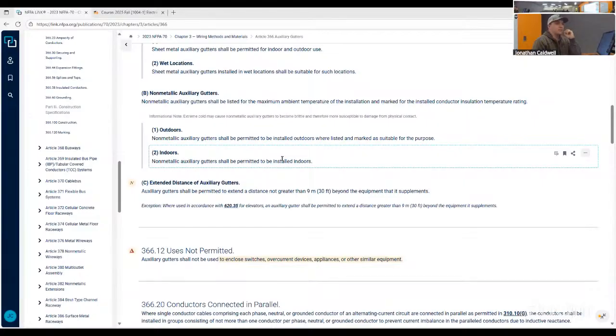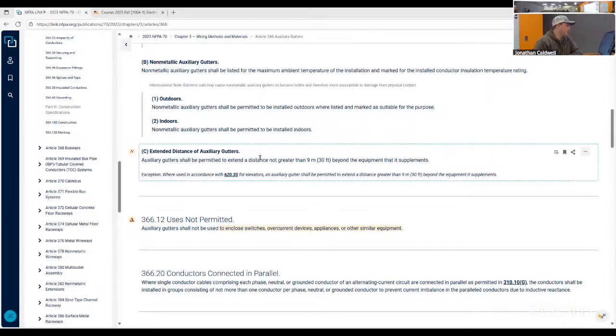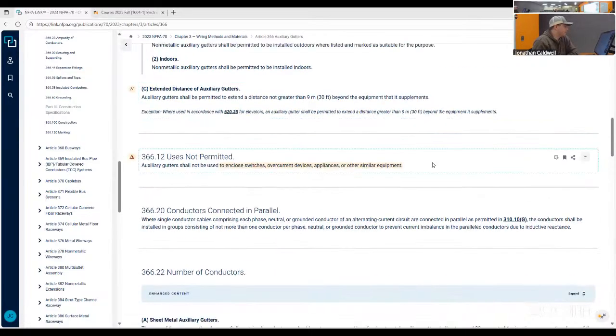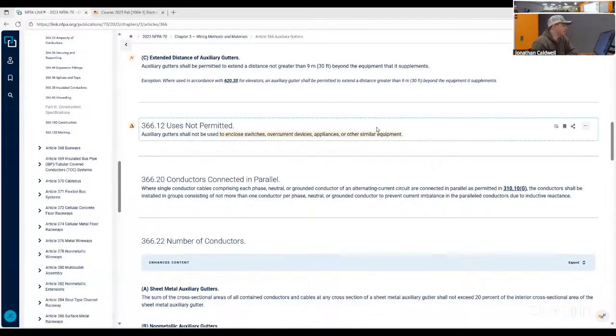That is one you measure twice and go from there, because you do not just measure once. Extended distance of auxiliary gutters. Gutters shall be permitted to extend a distance not greater than 30 feet beyond the equipment that it supplements. And for NEMA 1 gutters, they do make couplings and fittings and things like that you can buy, and they're relatively cheap. I can't think of any NEMA 3R ones or anything above that, because they're all handed and all that, but if you find one, let me know, please. I'm happy to look into that.